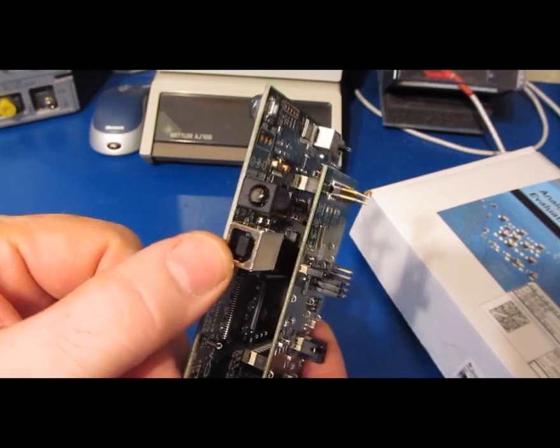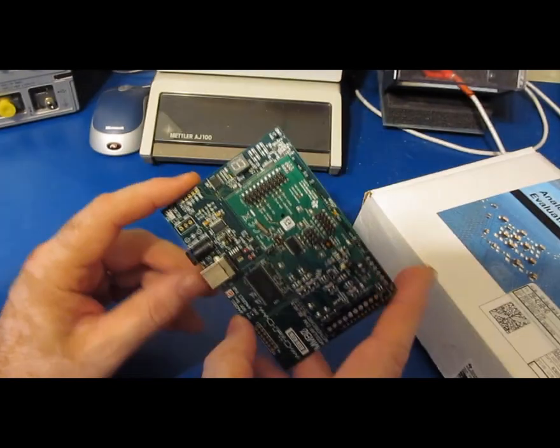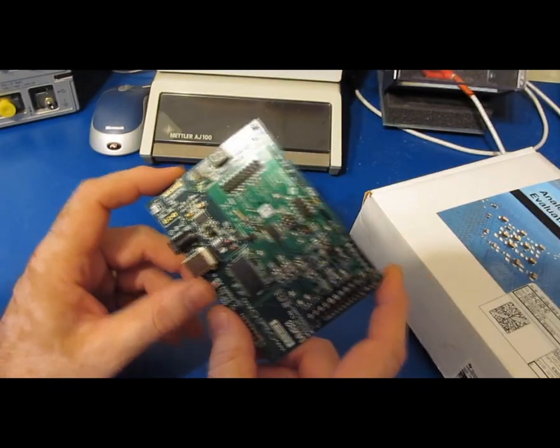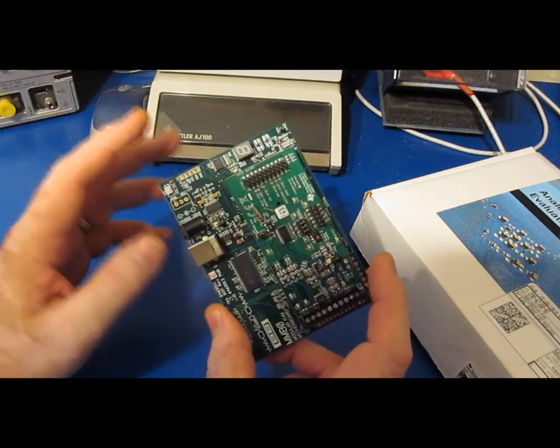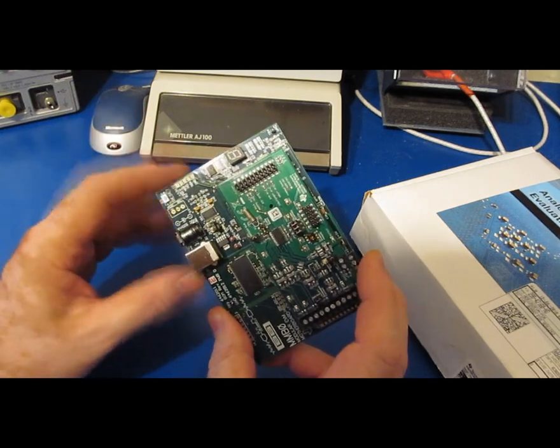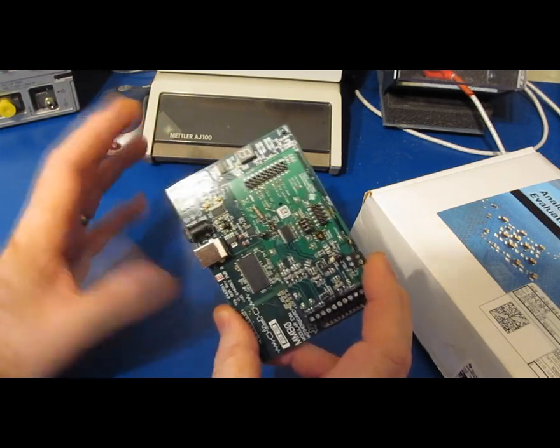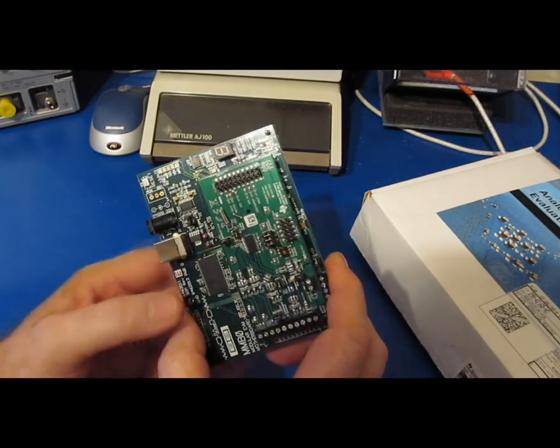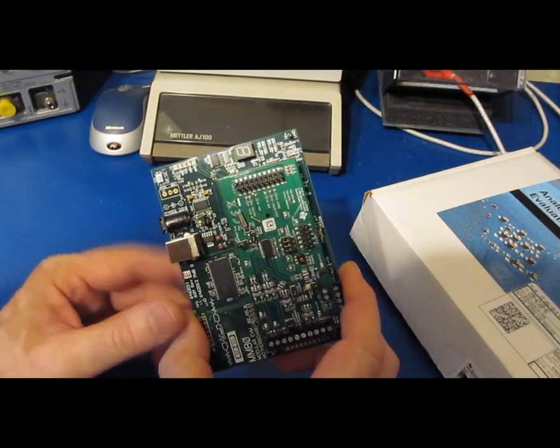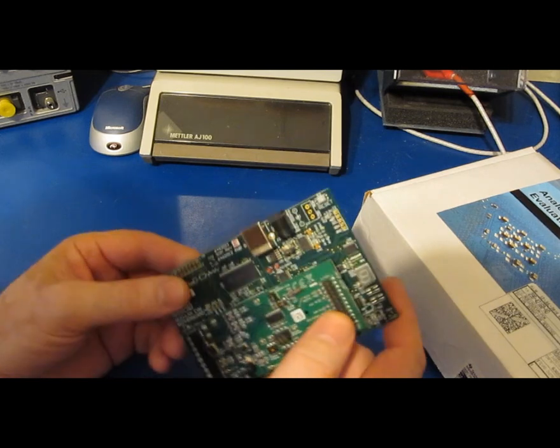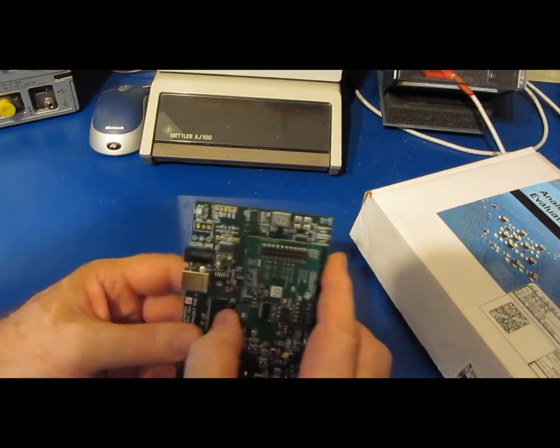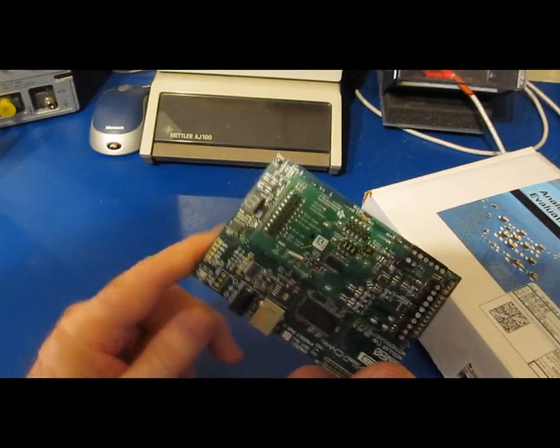This communicates to the PC using the USB bus. They supply you with LabVIEW source code for this. Unfortunately, LabVIEW makes all these underlying calls to a library which they don't supply the source code for, and unfortunately they didn't set this thing up to stream data. But because they did supply you with the source code, I was able to modify their code enough to where I could actually get this thing to stream the data.